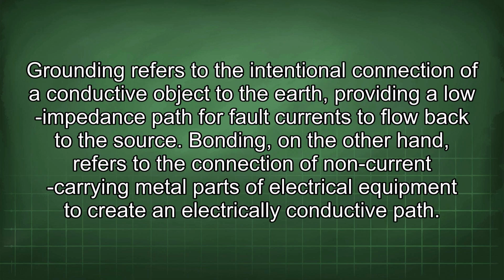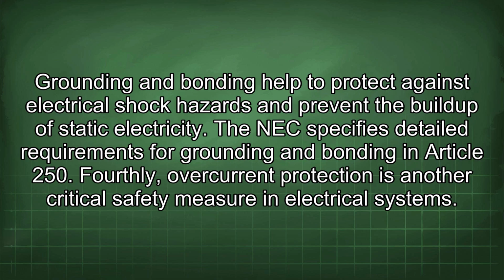Grounding refers to the intentional connection of a conductive object to the earth, providing a low impedance path for fault currents to flow back to the source. Bonding, on the other hand, refers to the connection of non-current carrying metal parts of electrical equipment to create an electrically conductive path. Grounding and bonding help to protect against electrical shock hazards and prevent the buildup of static electricity. The NEC specifies detailed requirements for grounding and bonding in Article 250.